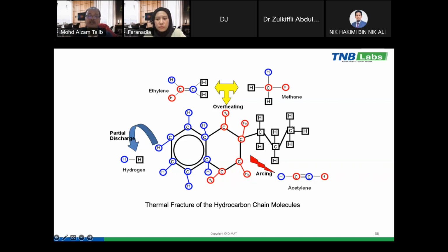For example, when we have an overheating fault, it will produce ethylene and methane gas, and if we have arcing in the power transformer, it will generate acetylene. When we extract hydrogen gas, it means that there is a partial discharge occurring in the power transformer. So through this chemical method, dissolved gas analysis, we extract the gas from the oil, and we analyze the gas. From the gas, we are able to differentiate the possible type of the fault, and one of the faults that we detect is partial discharge.